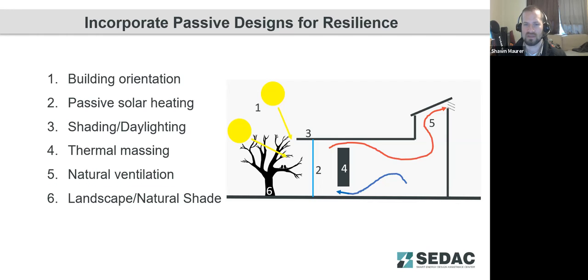Natural ventilation can also be an excellent way to help reduce the sizing of HVAC systems. You can take advantage of that to move air throughout the structure of the building and decrease the amount of mechanically provided outside air. So that can reduce the size of fans, blower systems, and duct systems, and you also get a benefit for the health of the occupants by bringing more outside air through the building. Many studies have shown that increasing the amount of outside air that flows through buildings beyond the minimum recommendations from ASHRAE has significant benefits for the health and the cognitive function of the occupants of the building.